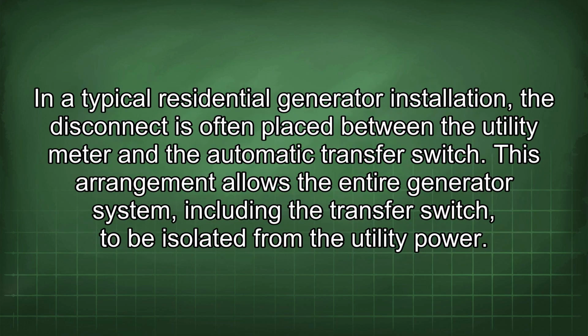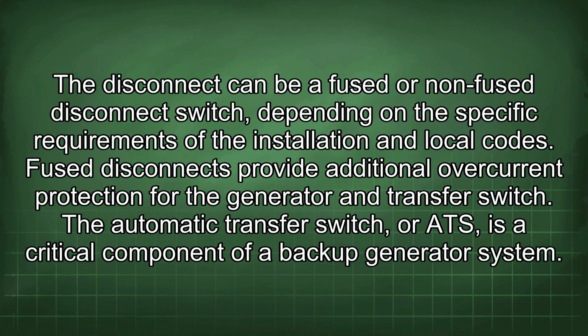In a typical residential generator installation, the disconnect is often placed between the utility meter and the automatic transfer switch. This arrangement allows the entire generator system, including the transfer switch, to be isolated from the utility power. The disconnect can be a fused or non-fused disconnect switch, depending on the specific requirements of the installation and local codes. Fused disconnects provide additional overcurrent protection for the generator and transfer switch.